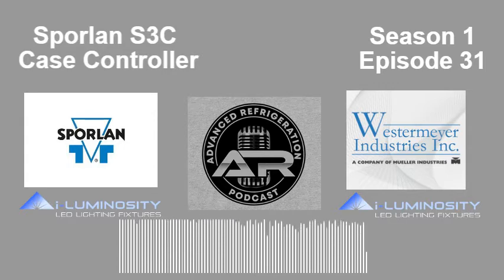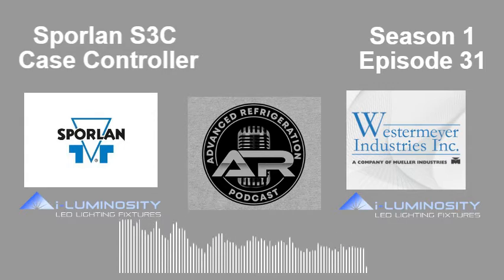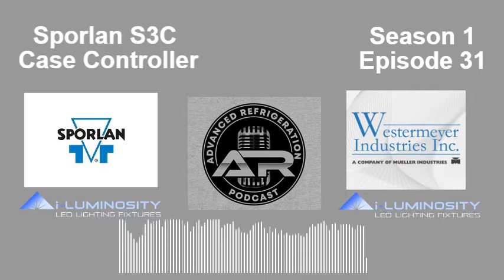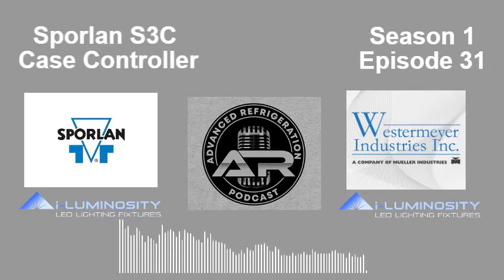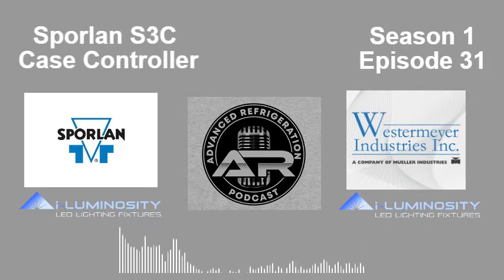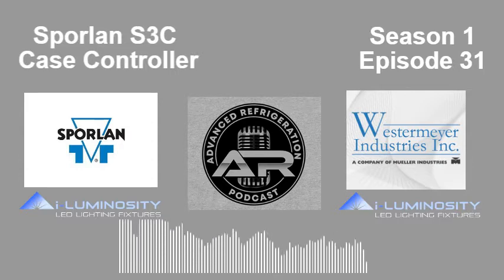And we've got a suggested set of procedures for you. It's a straightforward thing. You power down the controller, you disconnect the cables, you put the new controller in place, and you start connecting the cables, but you save the power cable for last. And that helps. That is a common thing that happens.